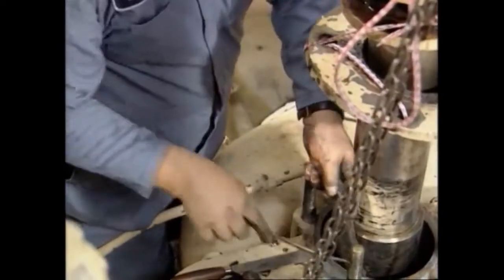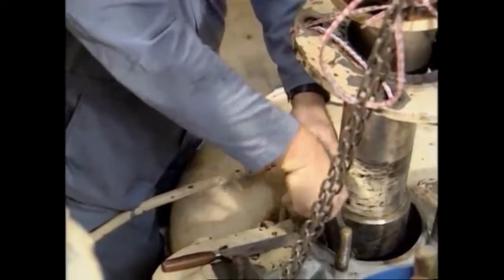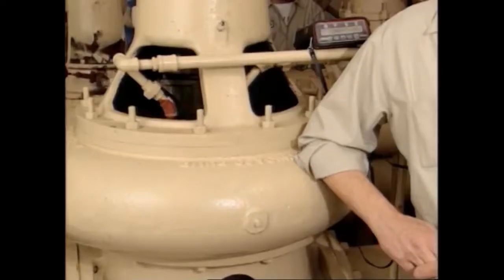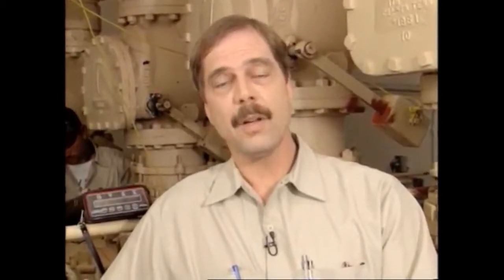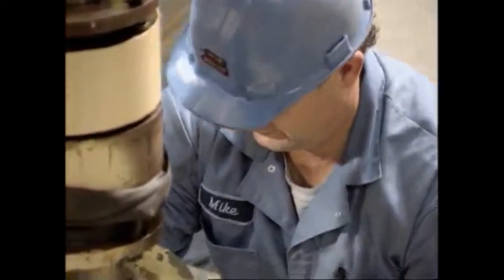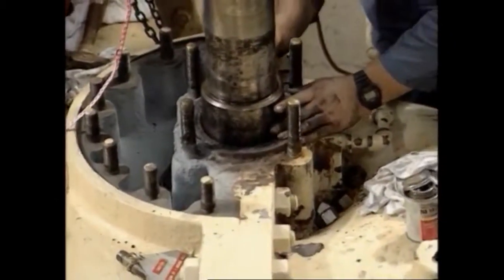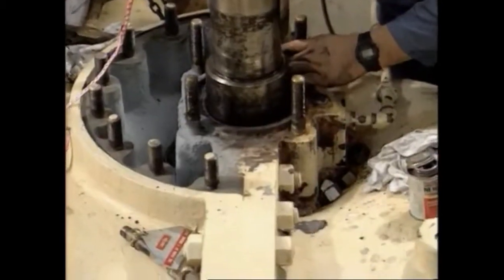If packing is not maintained properly, troubles can arise: shaft or shaft sleeve damage, waste or wastewater contaminating bearings, flooding of the pump station, and rust, corrosion and unsightliness of the pump and area. Finally, the suction head should not be allowed to go below the packing. Packing is used to provide a seal where the shaft passes through the pump case, to prevent air from being sucked into the pump case and also to prevent that which is being pumped from leaking out.